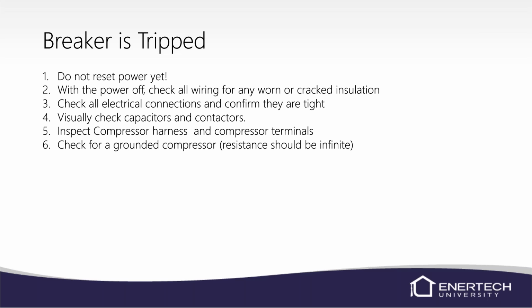Again, look at the compressor harness and the compressor terminals. Look for any excessive heat or any burning of those terminals. And also you can go ahead and check for a grounded compressor. Resistance should be infinite. If you're showing any resistance to ground, then the compressor is shorted to ground and your breaker is more than likely tripped.